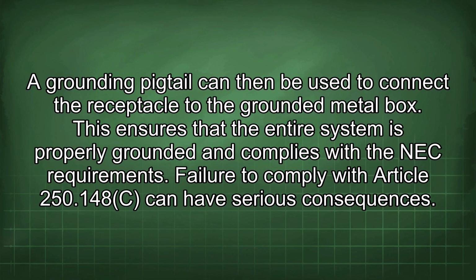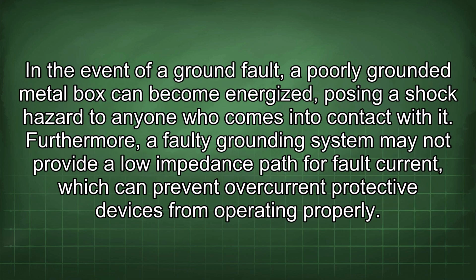This ensures that the entire system is properly grounded and complies with the NEC requirements. Failure to comply with Article 250.148c can have serious consequences. In the event of a ground fault, a poorly grounded metal box can become energized, posing a shock hazard to anyone who comes into contact with it.